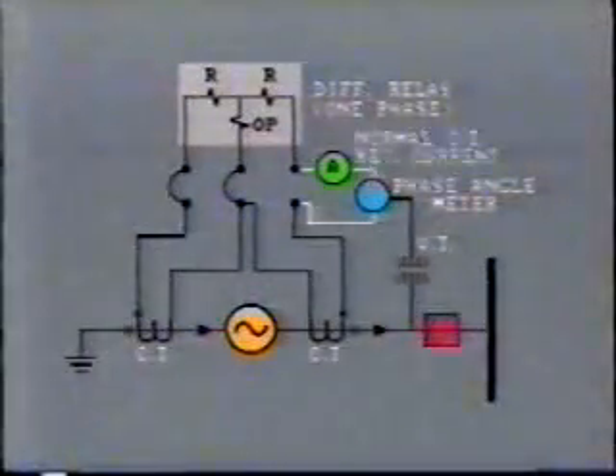The phase angle meter must be provided with a fixed voltage which can be used as reference in order to determine the phase angle and consequent direction of current. With a balanced load on the generator, the current passing through each relay operating coil should be at 0 or a very low value. On the other hand, current measured through the restraint coils should be equal to the CT secondary value. In any particular phase, the current through the restraint coils on either side should be 180 degrees apart.